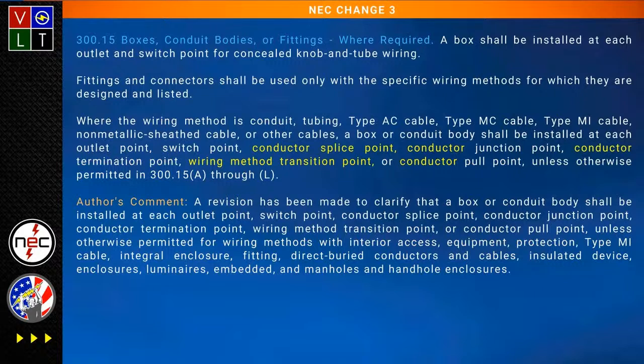It says any of those points are covered unless otherwise permitted for wiring methods with interior access, equipment protection, type MI cable, integral enclosure, fitting, direct burial cover, and so on. Basically it requires a box or conduit body for each of those points. That's where we started talking about, as a good example, the wiring method transition point. When we did that myth, I said they're going to clarify this in the 2023 because I'd already seen the change coming.